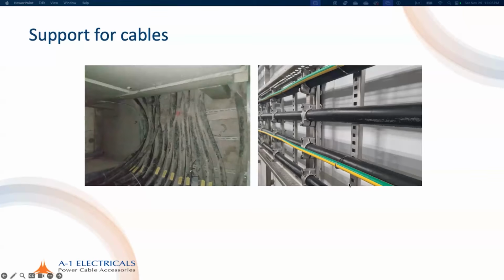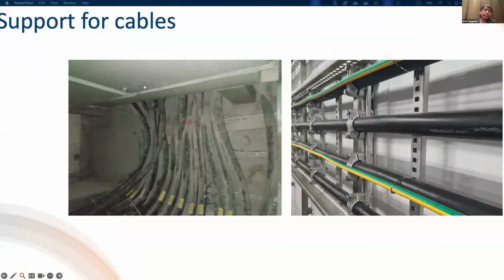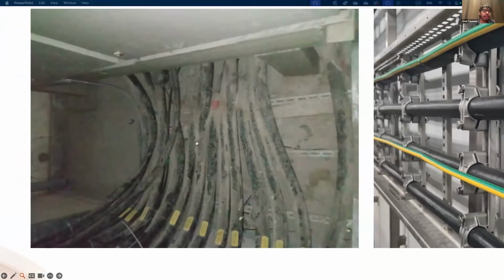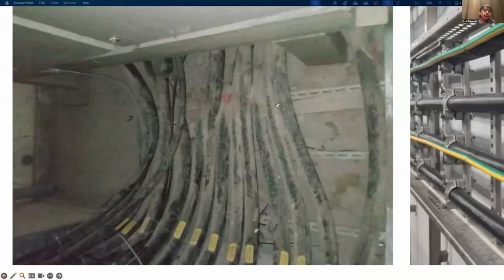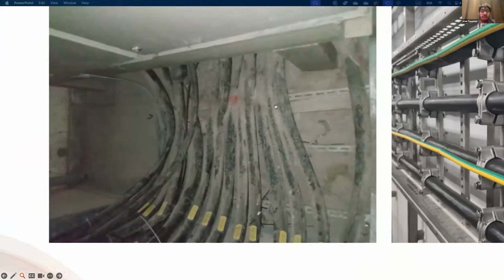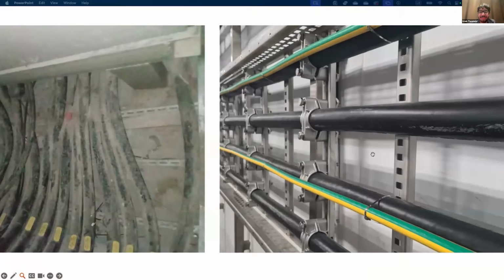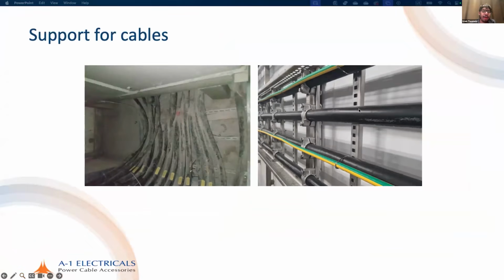Yeah. Now, we have seen what happens when cleats are not used and a short circuit occurs, right? And a short circuit that is interrupted. But in India, unfortunately, everywhere we see installations like this, where the cables are just dumped on the ladder or the cable tray. Spacing, forget about it. Over here, we see cables that are correctly installed and there are cleats. Very important. This is a cable tray surface. So when a short circuit occurs, you can imagine the force that will just rip through this.